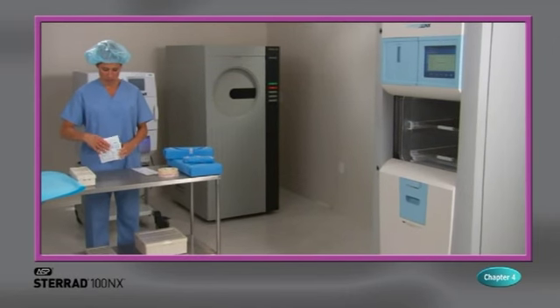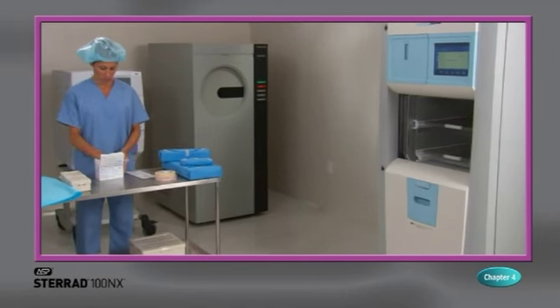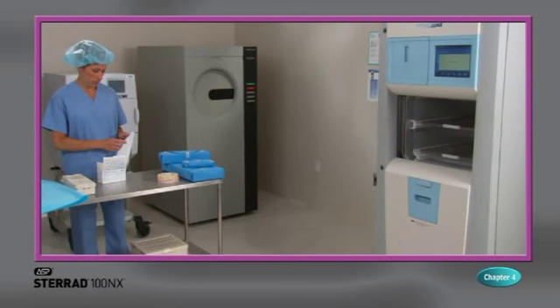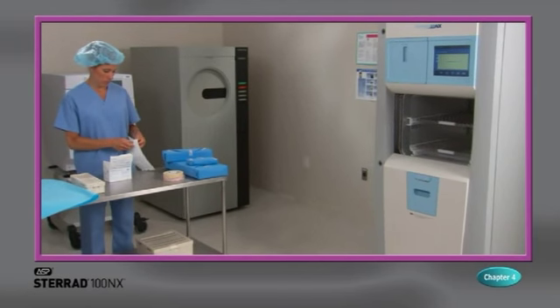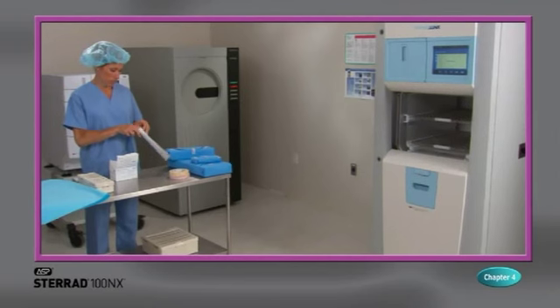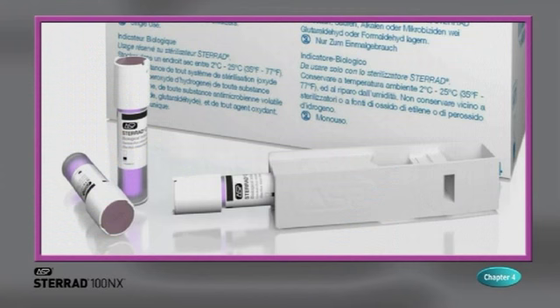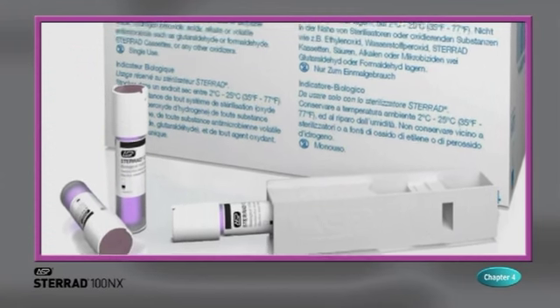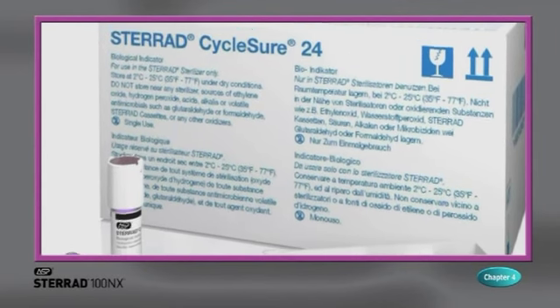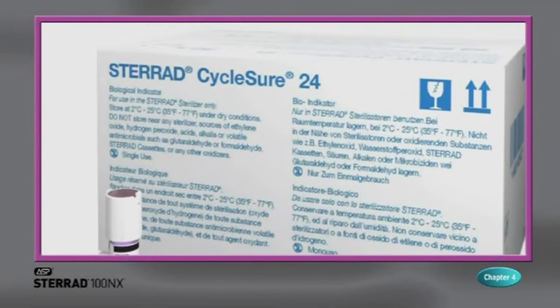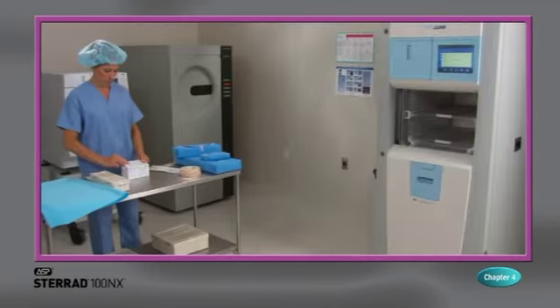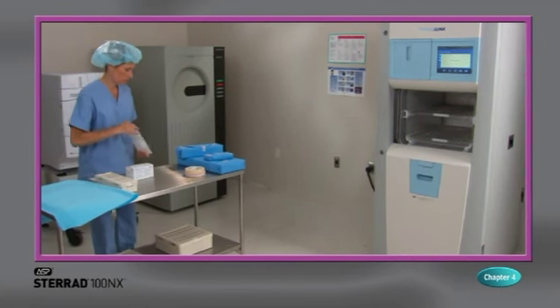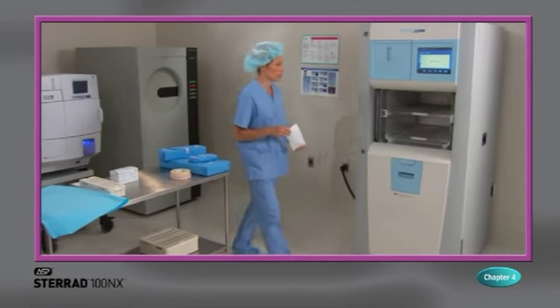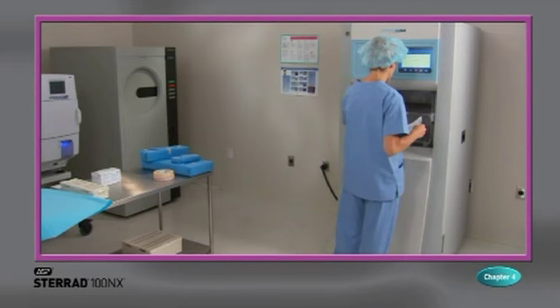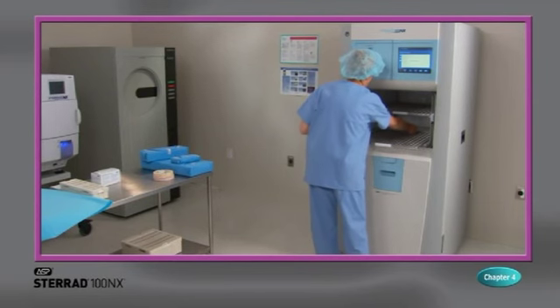Confirming that sterilizing conditions were achieved during a cycle is a critical part of the sterilization process. Biological indicators are one way to ensure that your sterilizer is operating correctly. ASP has validated all Sterrad systems using the Sterrad CycleSure 24 biological indicator. Place a Sterrad CycleSure 24 biological indicator in the most challenging area for the sterilant to reach. This is typically on the bottom shelf close to the rear of the sterilizer.